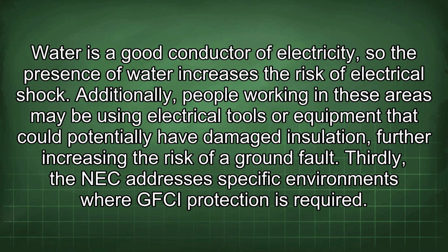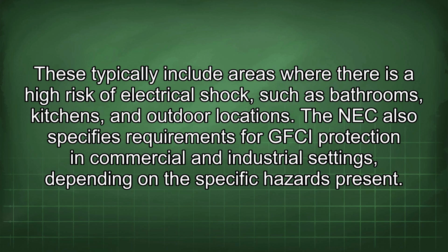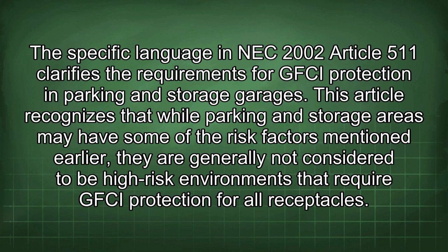Thirdly, the NEC addresses specific environments where GFCI protection is required. These typically include areas where there is a high risk of electrical shock, such as bathrooms, kitchens, and outdoor locations. The NEC also specifies requirements for GFCI protection in commercial and industrial settings, depending on the specific hazards present. The specific language in NEC 2002 Article 511 clarifies the requirements for GFCI protection in parking and storage garages.